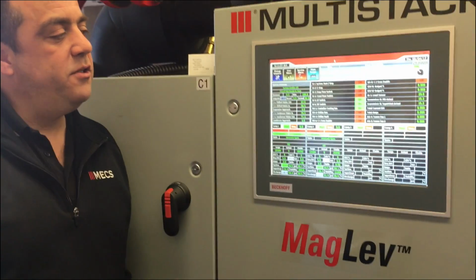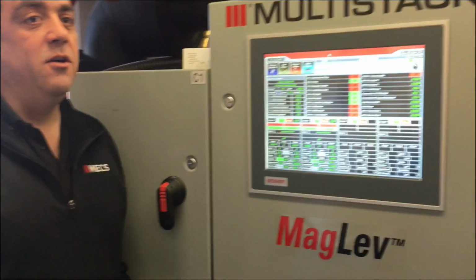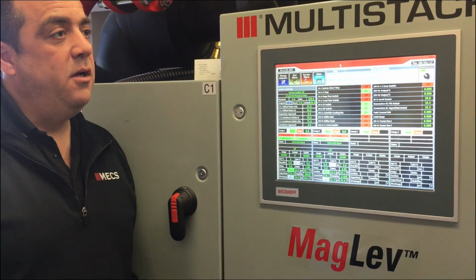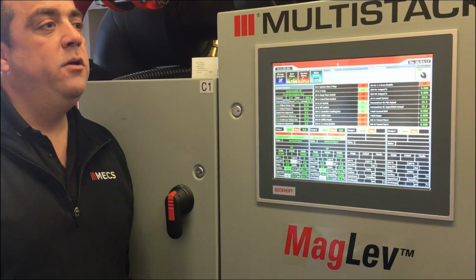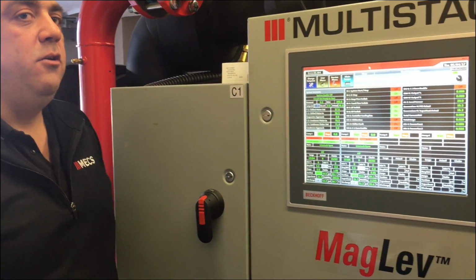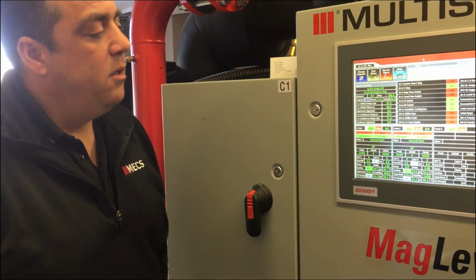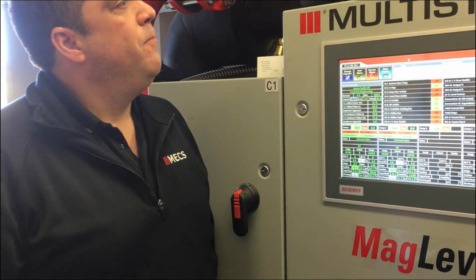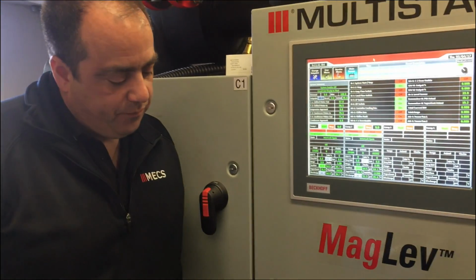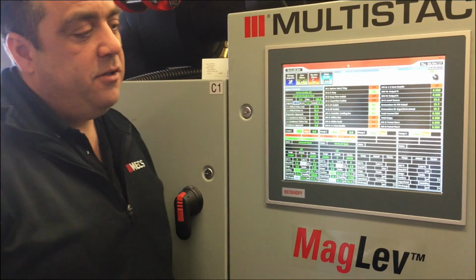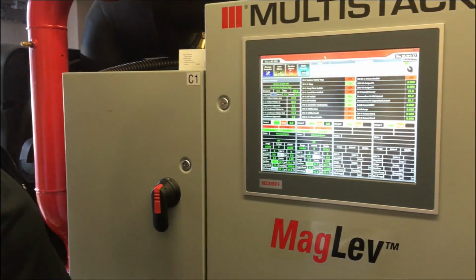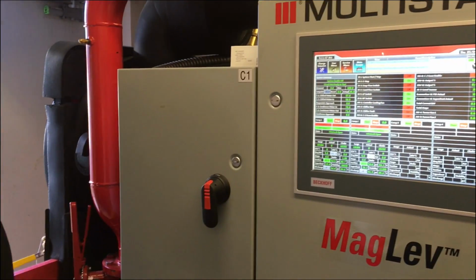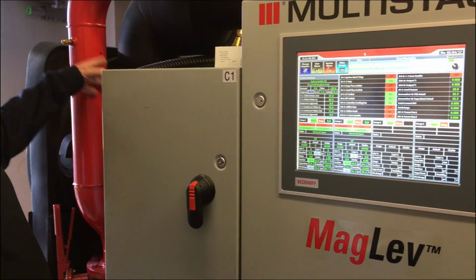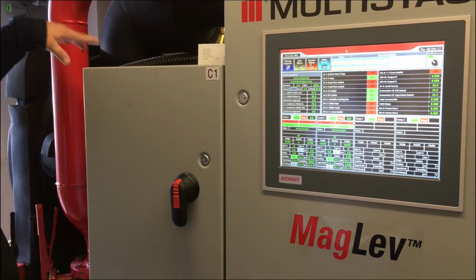No oil coolers, filters, none of all those things that would have been part of a regular chiller, they're out the window because there's no oil. So it's a huge chunk of maintenance that you toss out the door automatically, not having oil in the machine. Being a flooded machine, we have two barrels, the condenser and the evaporator. The condenser's down bottom, the evaporator's up top. The compressors sit directly on the evaporator inside the same circuit.